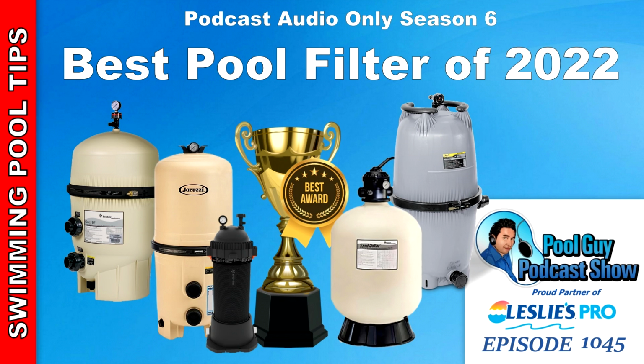And so the System 3 filters are actually great. I like them, but I don't think I would install one. They're expensive. The cartridges are extremely expensive, but if you have one on your route, I know you're going to like the System 3 filters because they're fairly easy to clean. You have that gigantic cartridge that sometimes is hard to get out, and you have those 8 clamps that go around it that are a pain, but if you have the multi-torque tool, it's really easy to get those off, and you're going to like the durability of the System 3 filter.